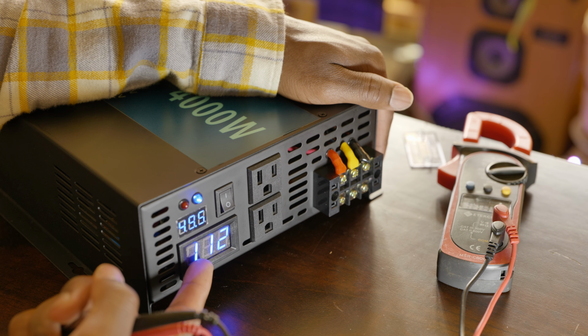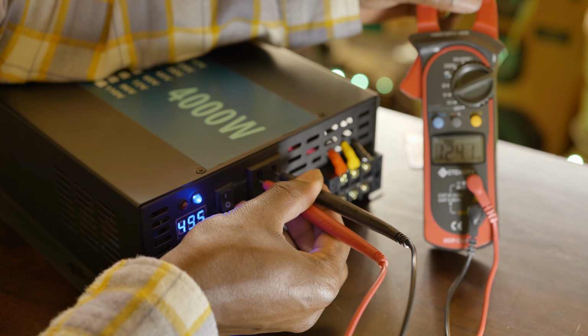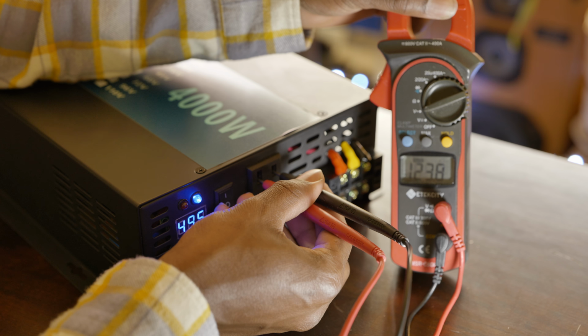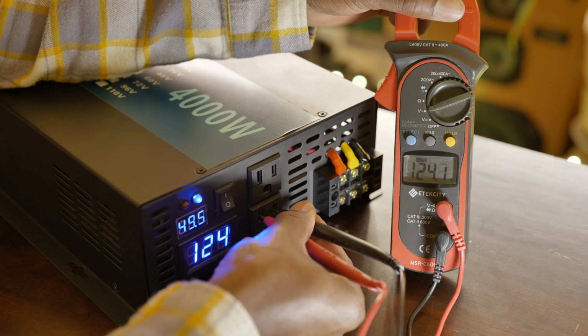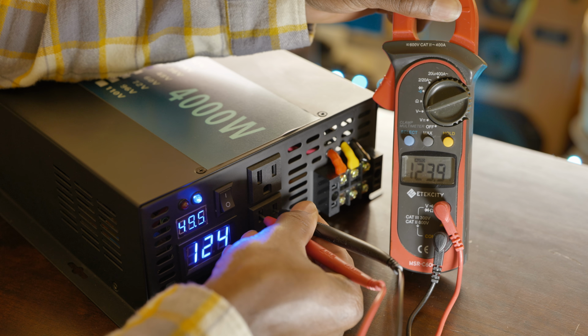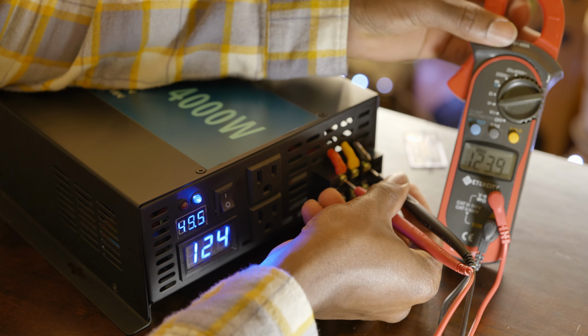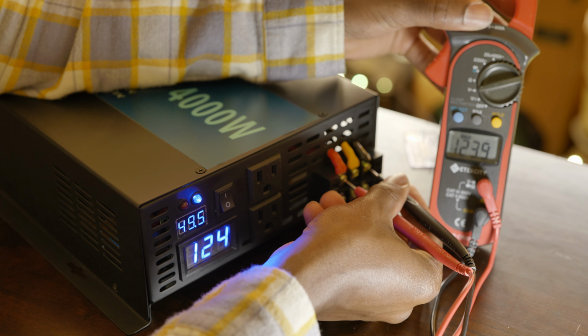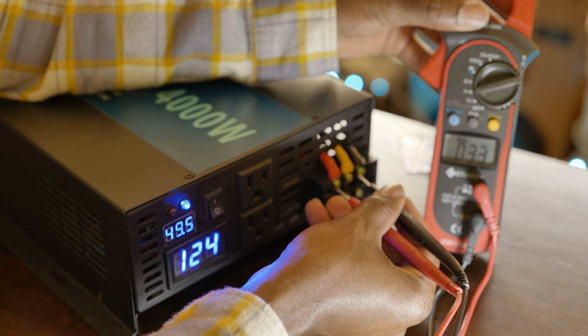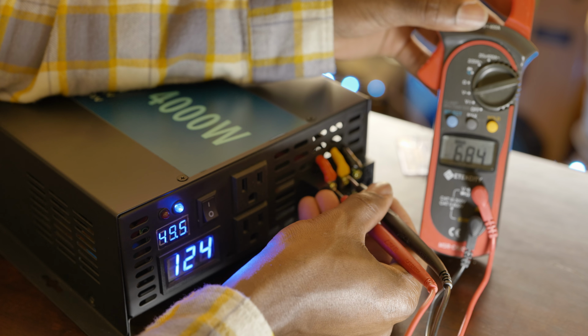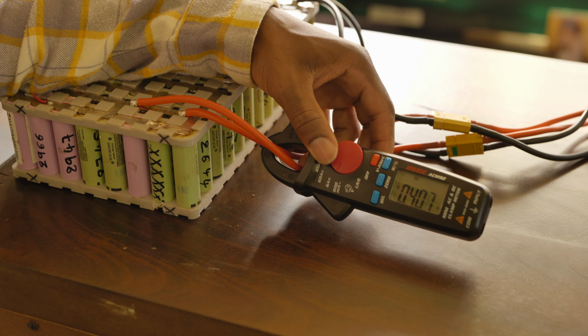As you can see, this goes up slowly: 124 volts, the second one 124, the terminal block 124. So from live to ground we have half the voltage, 66.6, and from neutral to ground we have the other half, 56.6. This is the standby current draw, 400 milliamps.